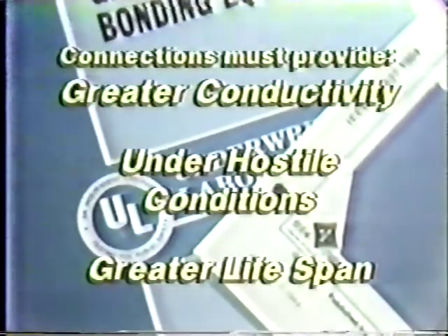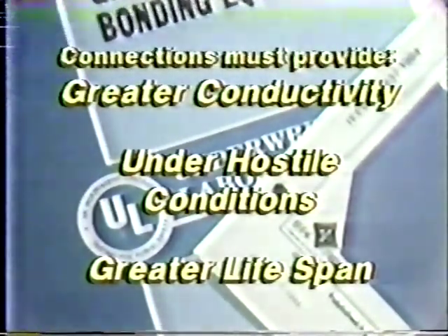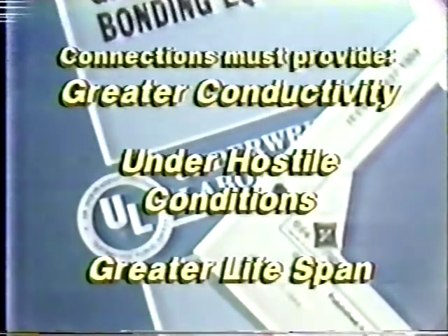Today's requirements and the extensive networking of power systems require switching equipment to deal with greater fault currents than ever before. As a result, newer regulatory specifications have been imposed to govern the grounding system design as well as the interconnection system used. Connections must now provide greater conductivity, operate under more hostile conditions, and continue to do this over a greater lifespan.